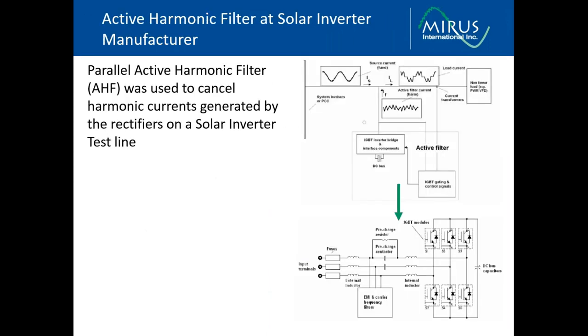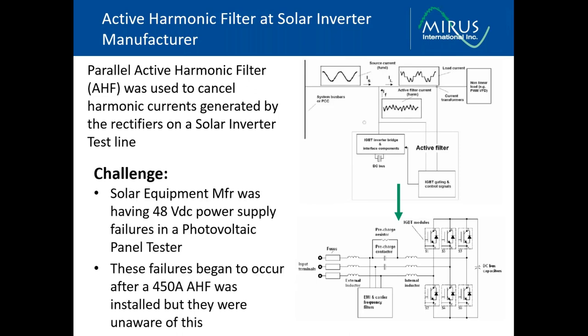This next example is a parallel active filter that was installed on a solar equipment manufacturing site in Toronto, Canada. The problem that they were having was with a 48-volt DC power supply that was part of a PV panel tester. As soon as they powered up that tester, the power supply would fail within a few minutes.